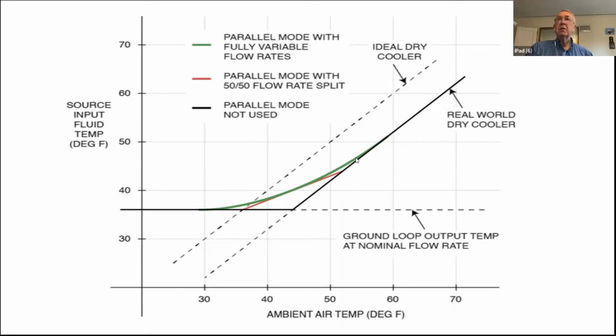But the bottom line is we have three different modes capable of choosing. The ground source mode when it's very cold, the parallel mode in the intermediate region, and we have an air source mode all the way up here. Of course, when we get up to 70 or higher for the ambient temperature, we don't need to use the heat pump at all. We just open the windows. Now, this same type of result would show up on the graph way up here off to the right, except that's the example where we need cooling for the building rather than heating.